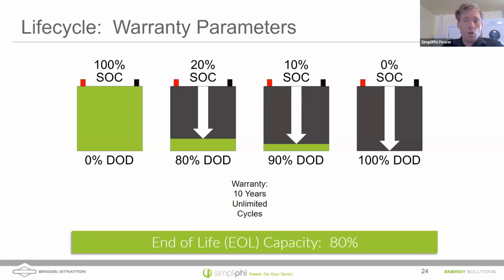So if we charge every single time and discharge every single time to 100% depth of discharge, we are only expecting a little over 3,000 cycles out of our batteries, right? And 3,000 cycles is still a lot. That's more than you get out of a normal lead acid battery. But again, if your battery is just sitting there for that occasional power outage, it's going to take you a long time before you get 3,000 power outages that drain your battery 100% every time. And that's why Daniel's saying, yeah, if you've got battery backup, go ahead and discharge to 100% depth of discharge, completely covered under a warranty.